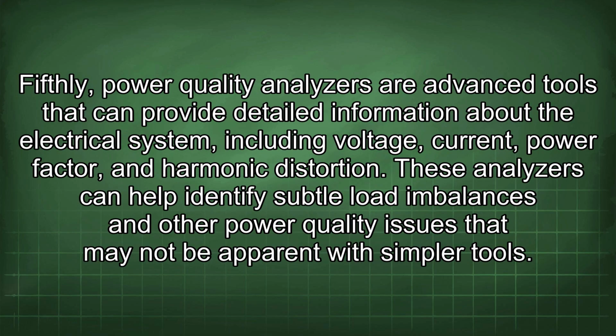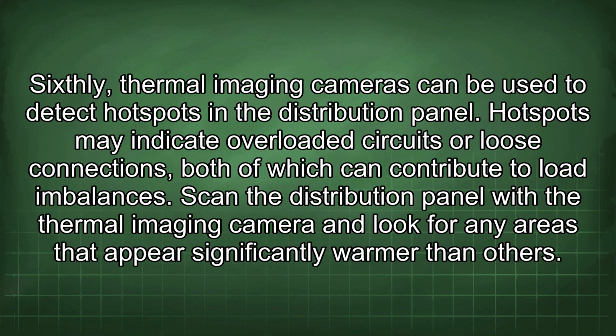Fifthly, power quality analyzers are advanced tools that can provide detailed information about the electrical system, including voltage, current, power factor, and harmonic distortion. These analyzers can help identify subtle load imbalances and other power quality issues that may not be apparent with simpler tools. Sixthly, thermal imaging cameras can be used to detect hotspots in the distribution panel. Hotspots may indicate overloaded circuits or loose connections, both of which can contribute to load imbalances. Scan the distribution panel with the thermal imaging camera and look for any areas that appear significantly warmer than others.